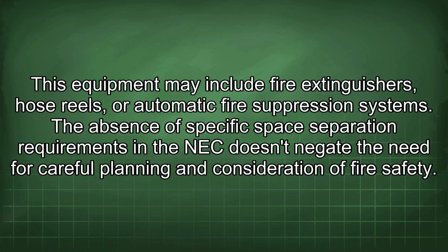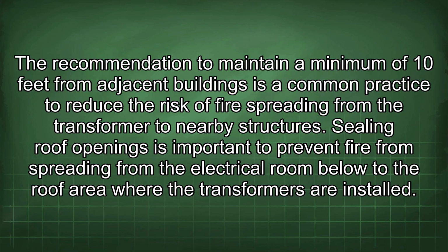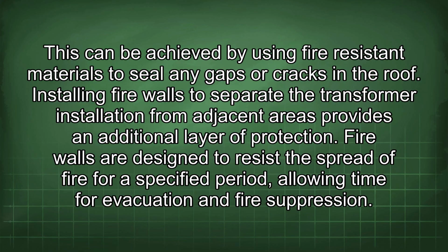The absence of specific space separation requirements in the NEC doesn't negate the need for careful planning and consideration of fire safety. The recommendation to maintain a minimum of 10 feet from adjacent buildings is a common practice to reduce the risk of fire spreading from the transformer to nearby structures. Sealing roof openings is important to prevent fire from spreading from the electrical room below to the roof area where the transformers are installed. This can be achieved by using fire-resistant materials to seal any gaps or cracks in the roof. Installing fire walls to separate the transformer installation from adjacent areas provides an additional layer of protection. Fire walls are designed to resist the spread of fire for a specified period, allowing time for evacuation and fire suppression.